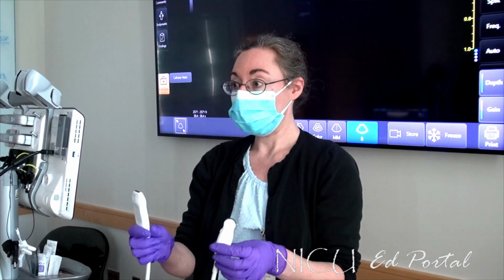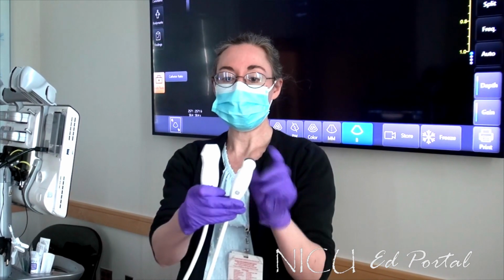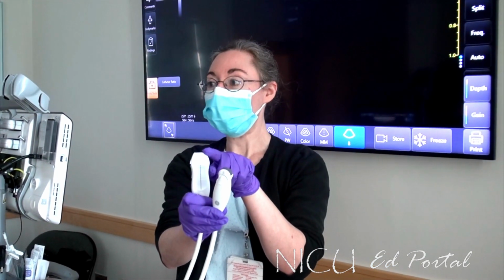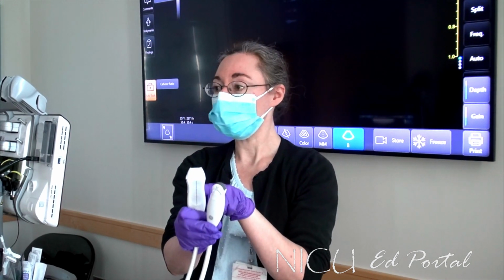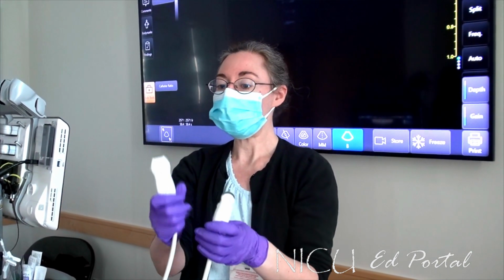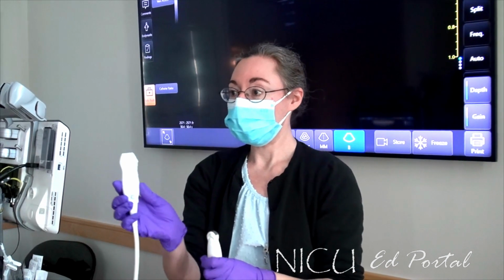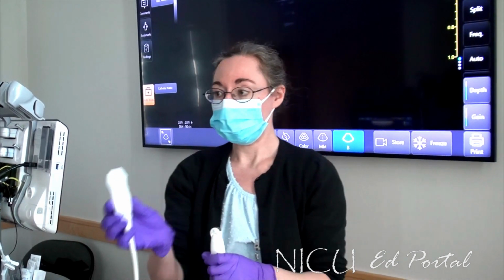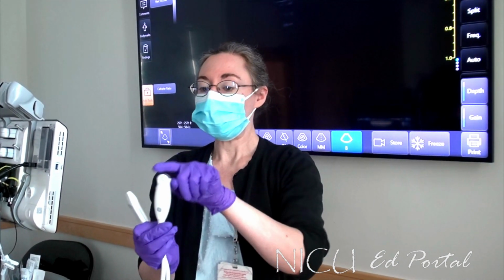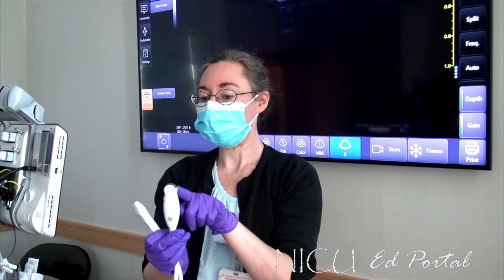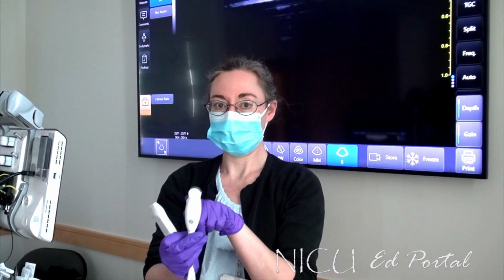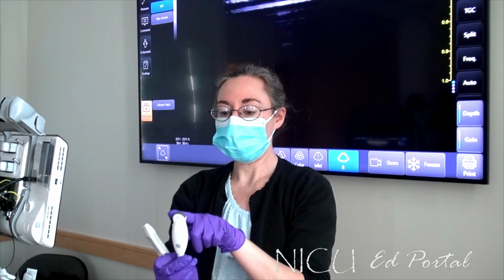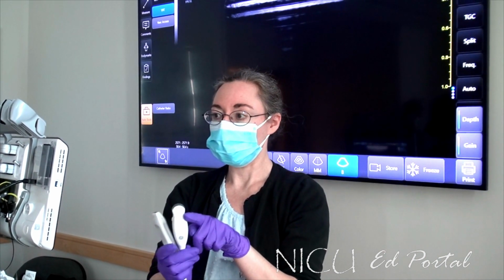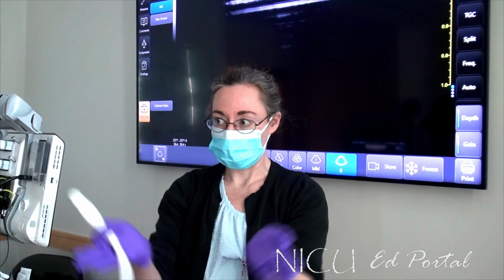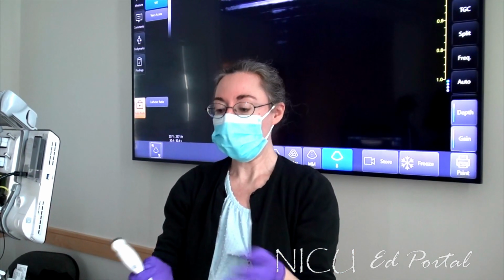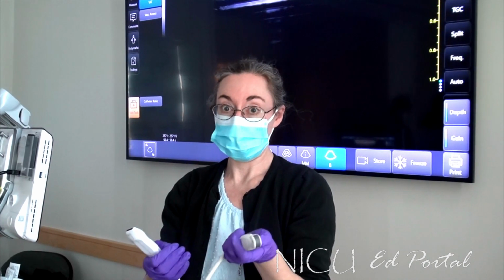The other way we define the probes is by the footprint. The shape of this probe is flat, it's linear. This is a high frequency linear probe, and it says here on the probe L 10 to 22, which means linear 10 to 22 megahertz. This one is a curved footprint, and it says 8C, which means 8 megahertz curved. That means you're going to get a wider field of view with the curved probe, because instead of a rectangular footprint, it has more of a triangular footprint. And that's important when you're looking at deeper structures.